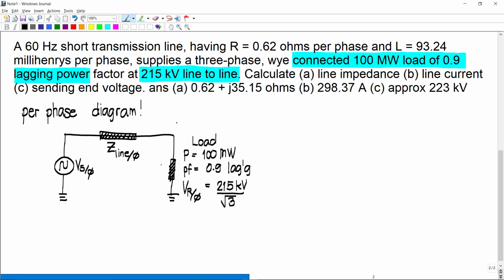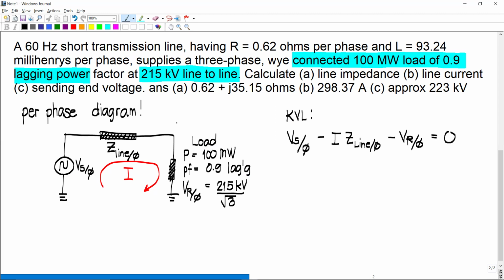So what will be our solution here? Since we have a load connected through the line to the source, there comes now the flow of current. So if we apply KVL, starting from the per phase sending end voltage, we subtract the voltage drop in the transmission line, which is the product of the current and the impedance of the line per phase. We also subtract the voltage per phase at the load, and this is equal to zero.